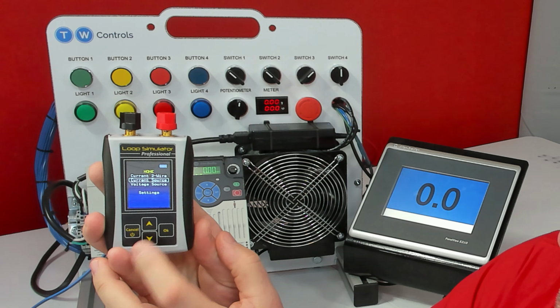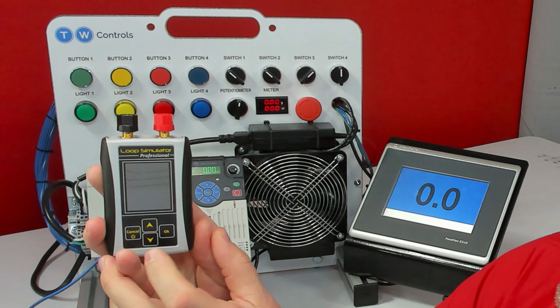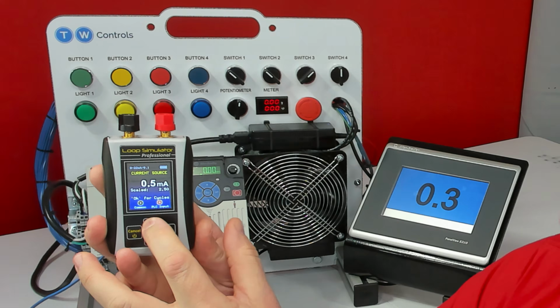Now I'm going to put the Sim ALP2 into current source mode. And as I bring the value up, it matches on the HMI. And in our function block, we can see our raw value coming in and our scale value coming out.